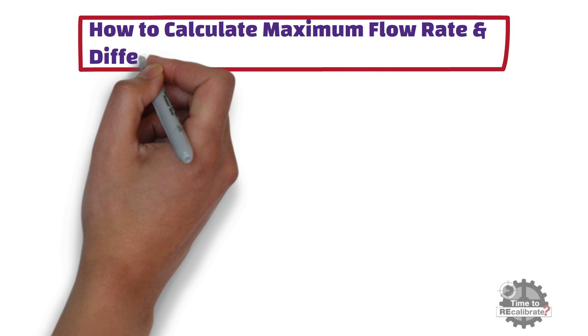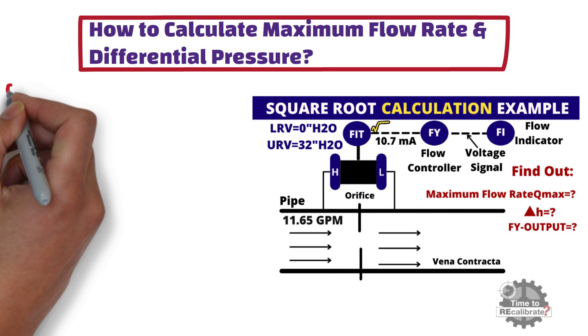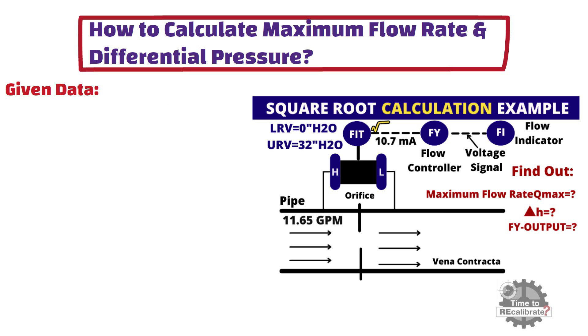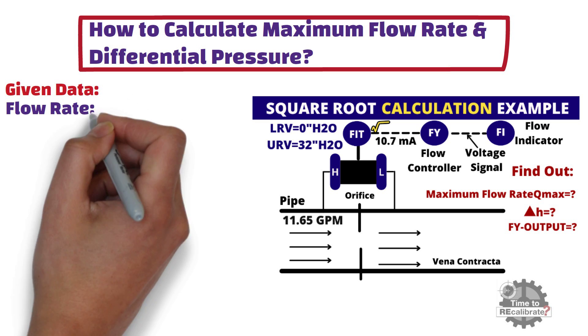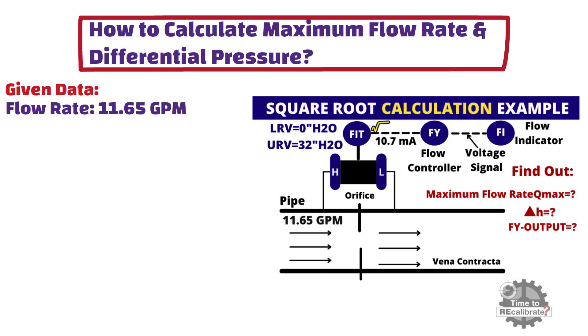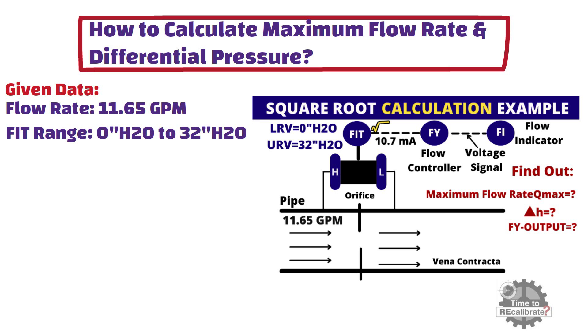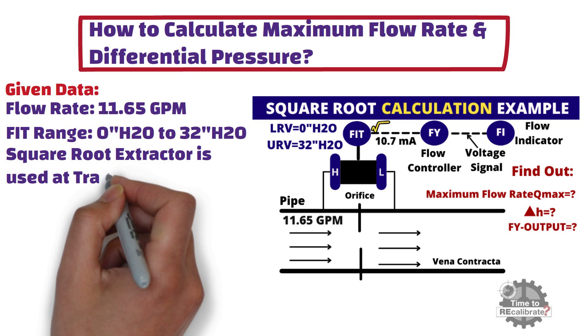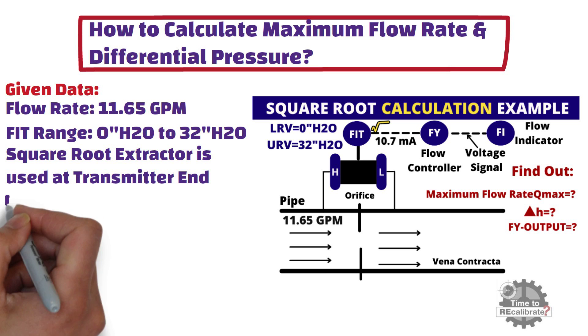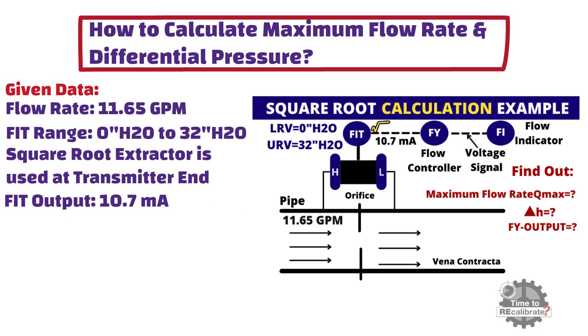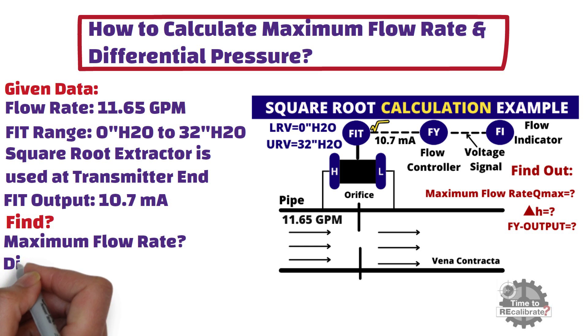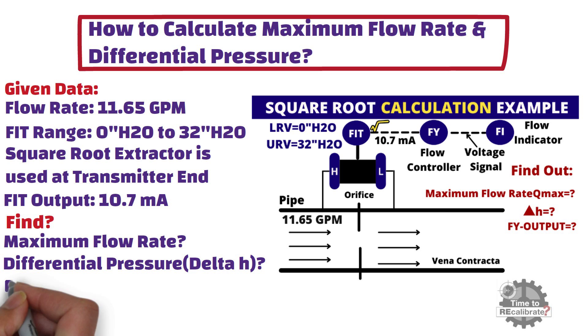First, let's learn how to calculate maximum flow rate and differential pressure in the following example. We will write down all the information already given: flow rate is 11.65 GPM, the range of the flow indicator transmitter is 0 to 32 inch H2O, a square root extractor is being used at the transmitter end, and 10.7 mA is the output of the transmitter. Using this information, we will calculate maximum flow rate, find differential pressure, and lastly calculate flow controller output.